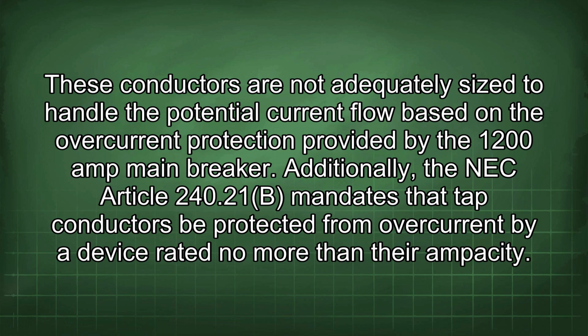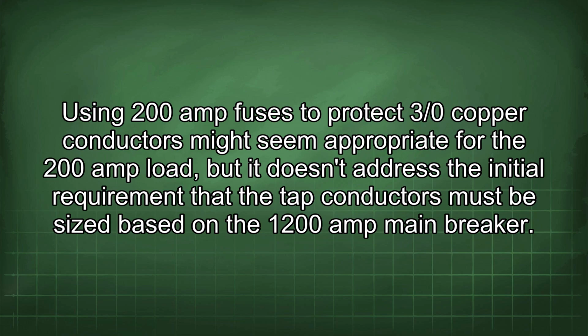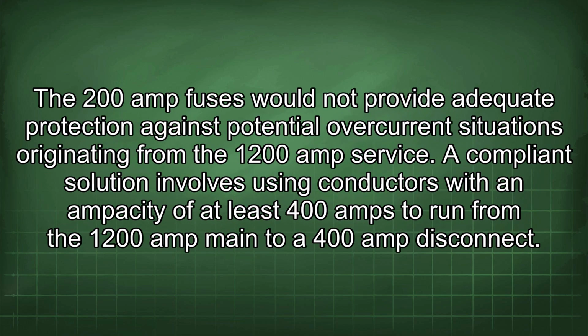Additionally, NEC Article 240.21(B) mandates that tap conductors be protected from overcurrent by a device rated no more than their ampacity. Using 200 amp fuses to protect 3/0 copper conductors might seem appropriate for the 200 amp load, but it doesn't address the initial requirement that the tap conductors must be sized based on the 1200 amp main breaker. The 200 amp fuses would not provide adequate protection against potential overcurrent situations originating from the 1200 amp service.